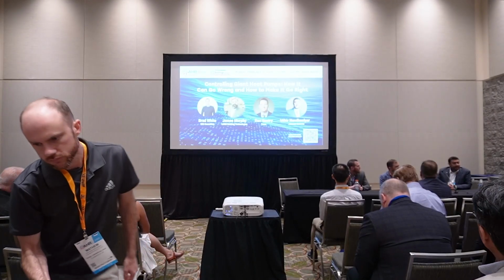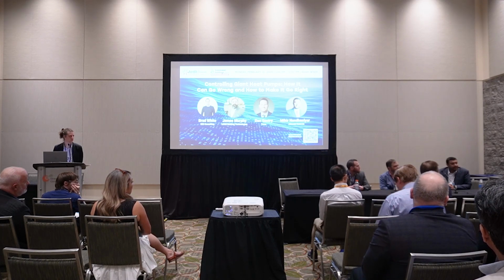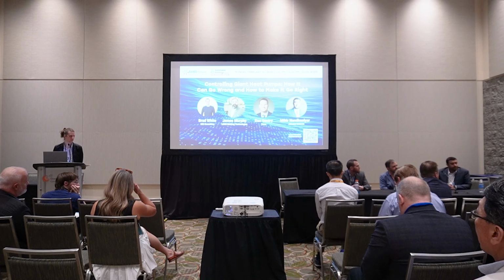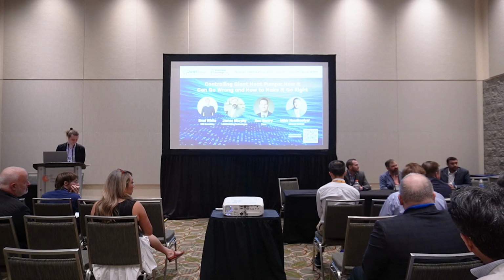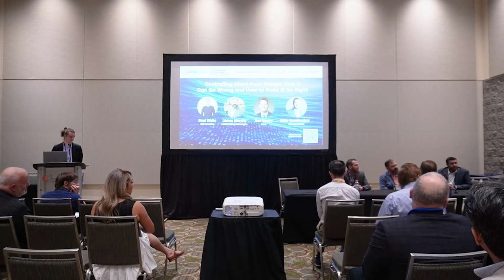So I'm not sure what the anti-recycle option is. I thought it was like an anti-short cycling, so you get that really low load, there's not quite enough BTU, you hit your set point, unit's on for 30 seconds, shuts off. I literally just say you have to be on for this amount of time and off for this amount of time. That's how I do that. Is that good? But is that the BMS, or is there controls built into the unit?